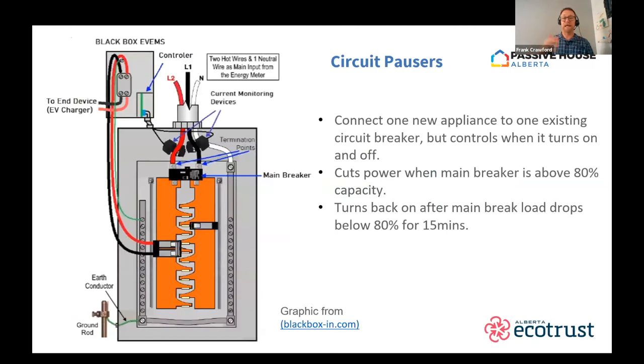The other type is called a circuit pauser. This one connects to one breaker on the panel and sends that to a box, and that box then connects to your new appliance, a single appliance, or it could be a sub panel if you wanted. It controls when power goes to that new appliance by monitoring the main power on the panel. If it goes above 80% or a set value, then it turns off the power to that new appliance. Once it drops back down, then it turns the power back on.